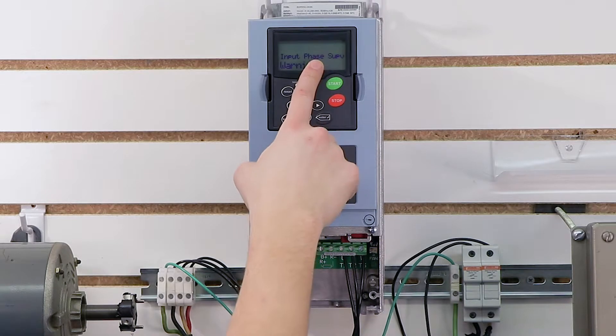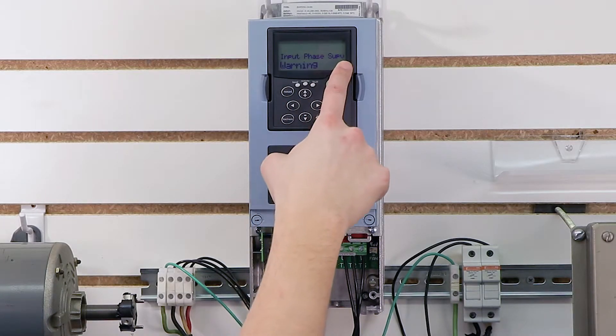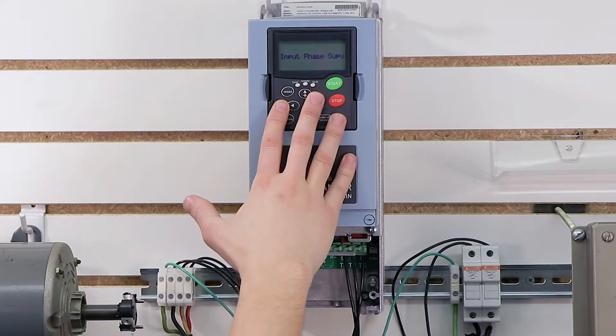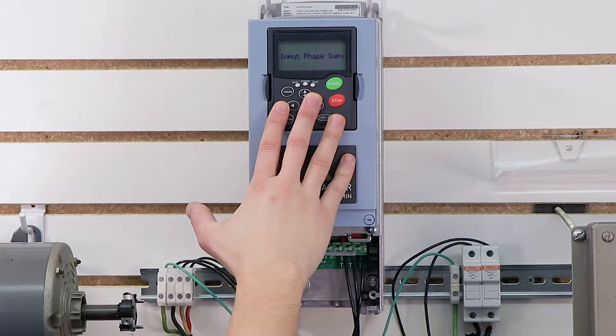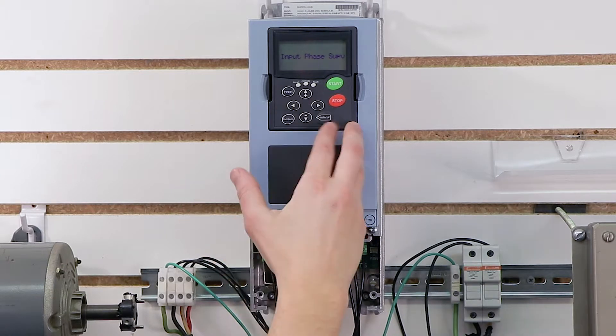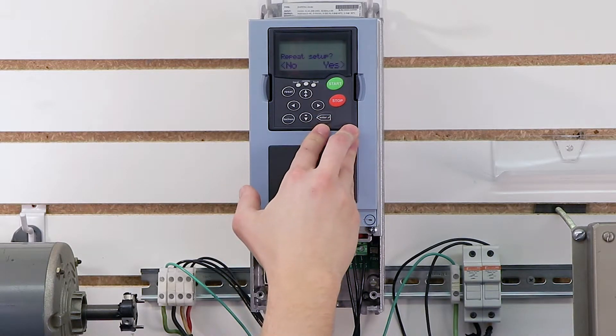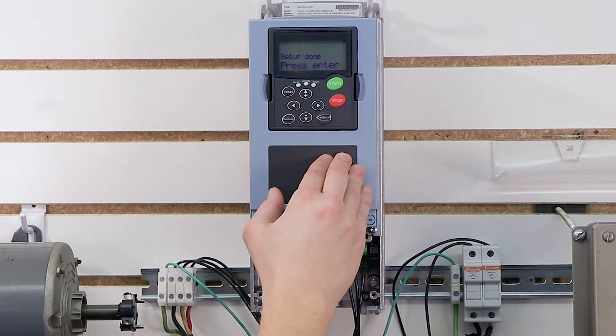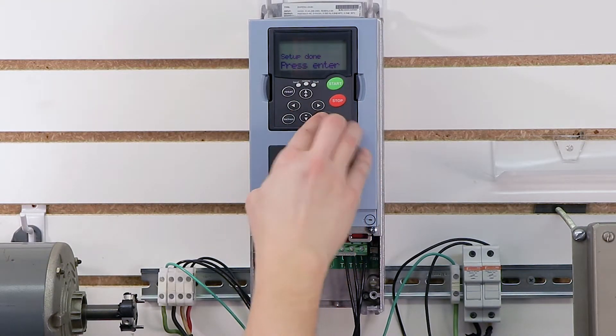Now I'm getting a warning that says input phase supervision. Now this is because if you watched my previous video, I'm actually running this drive on single phase input for this demo. When you have three phase coming in, you're not going to get this warning. I can actually turn that off later if I wish. Finally, it's asking me if I want to repeat my setup. I'm going to say no. And setup is done. Press enter.